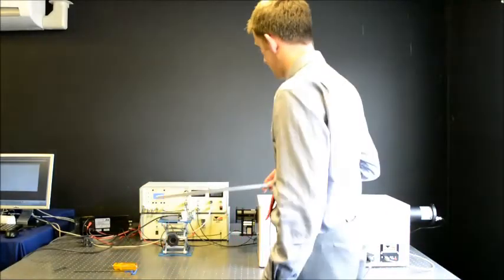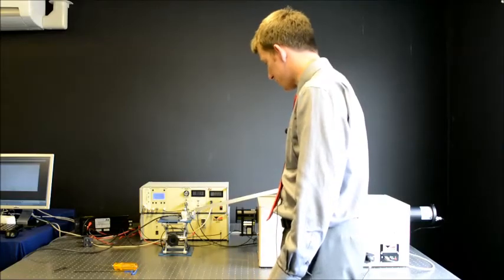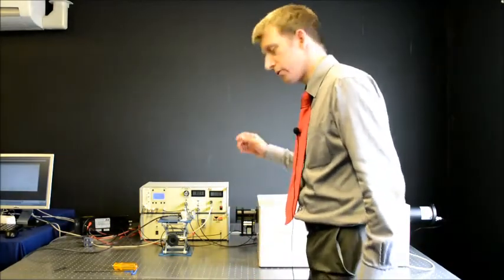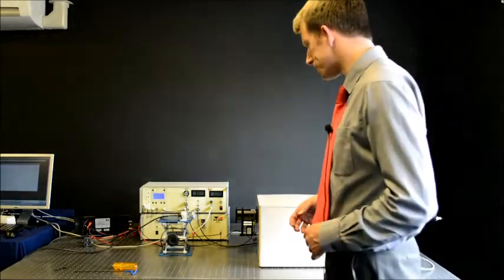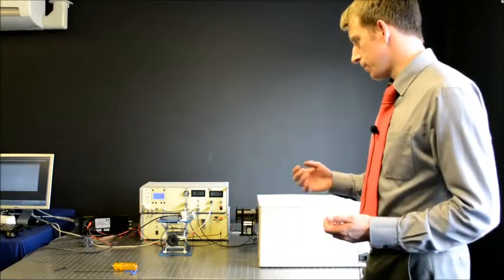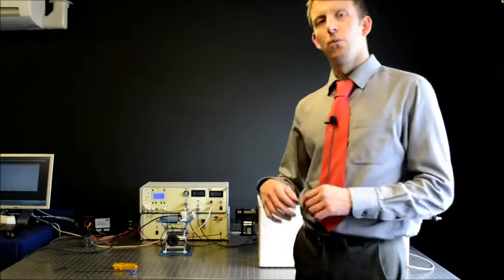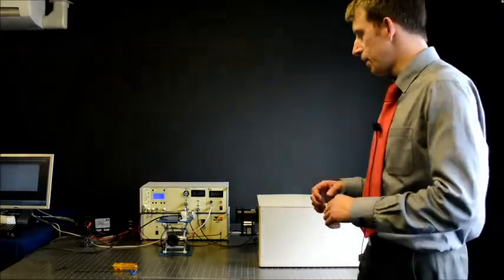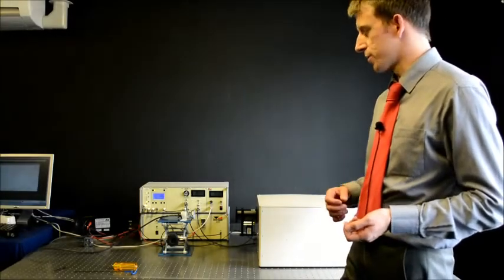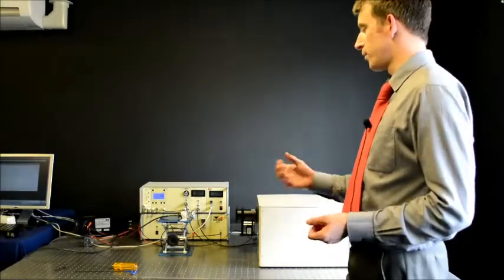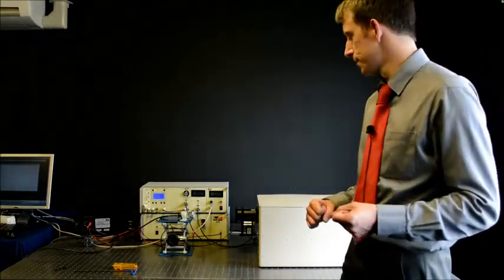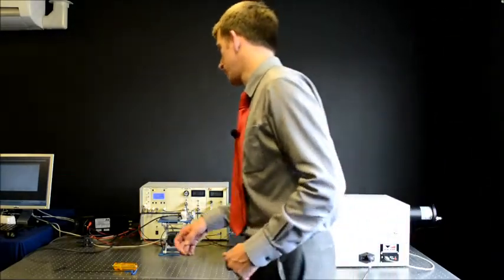We set up approximately 200 millimeters from the source to the front face of the relay optic. Again, this is a relative measurement, so there's no real importance in having any particular measurement distance. The measurement we will perform here will, when you do this correctly, be attached, as we've said, to measurements of the irradiance of the source between 200 and 1100 nanometers, or certainly up to 1100 nanometers, which we've not looked at in this series of videos. So we will power the source on.